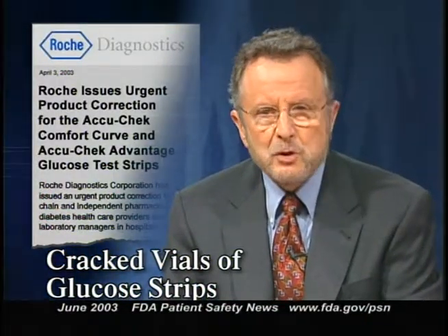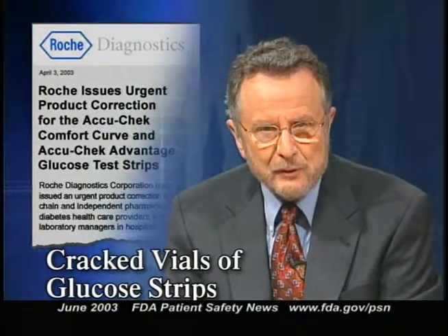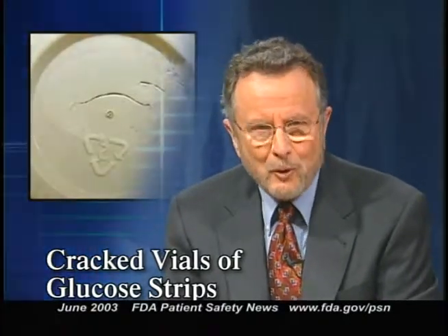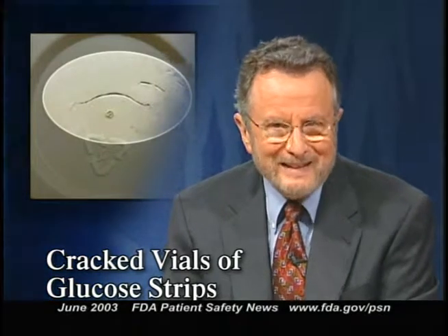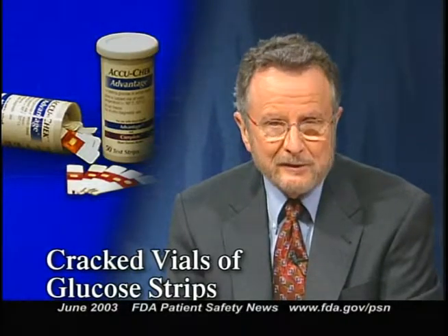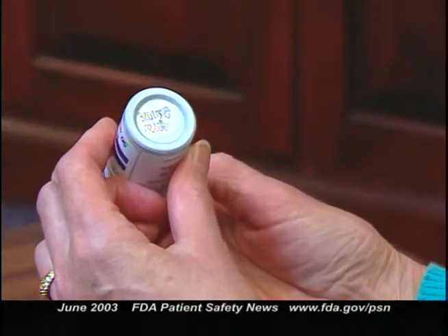Roche Diagnostics Corporation has issued an urgent product correction on some of its Accu-Chek glucose test strips because of a defect in the vials that hold these strips. The problem is that some vials may be cracked and allow moisture to get in, causing inaccurate results. The affected brands are Accu-Chek Comfort Curve and Accu-Chek Advantage test strips. The manufacturer believes only a small percentage of vials are affected. Cracks may develop at any time, including after the vial has been opened. Roche is asking users to inspect the bottom of every vial for cracks before each use and not use test strips from a cracked vial. If there's no crack but blood glucose results are unusually high, low, or inconsistent, the test should be repeated along with a quality control check.